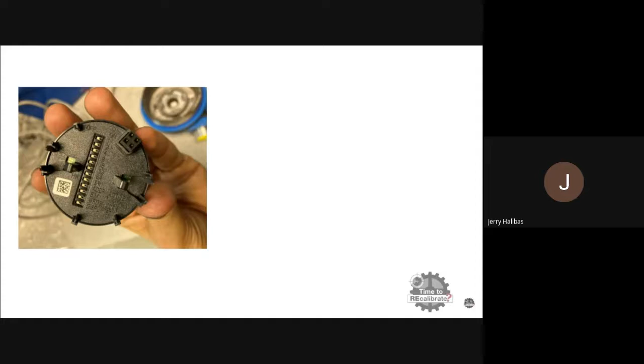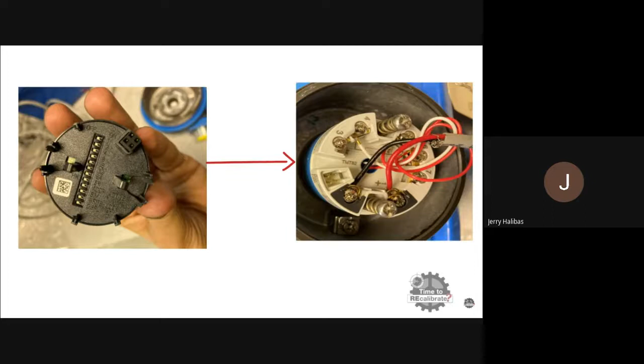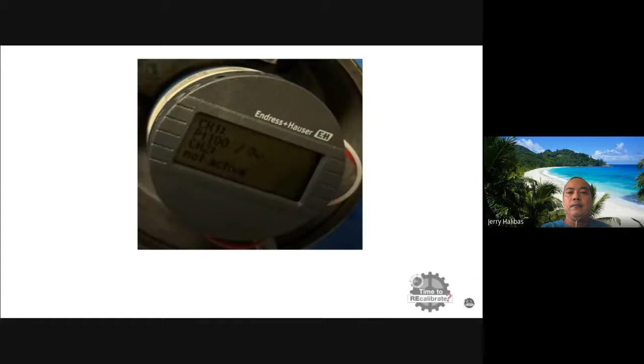Now we are done with wiring. So, connect the display to the transmitter, and check it's working by putting the RTD in a temperature bath. Once the working is confirmed, we can take out the power supply connections, and mount the RTD on-site for process operations.